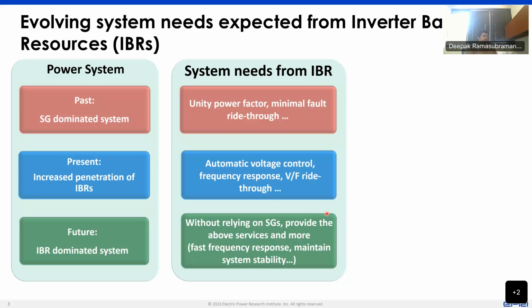But as we move further on to a future system that is IBR dominated, and maybe to some extent in a few hours of the day even 100% IBR, we do want to have more services from these inverter-based resources. Fast frequency response could be one of them. We want them to help maintain system stability, maybe voltage control. Some of them could be black start, contributing to damping margins, and so on. So the list of services that we would require from these resources would just continue to grow, because we've been so accustomed to that being provided by synchronous generators, which may do it naturally, but for it to be coded up in an inverter-based resource control, we really need to list them out explicitly.